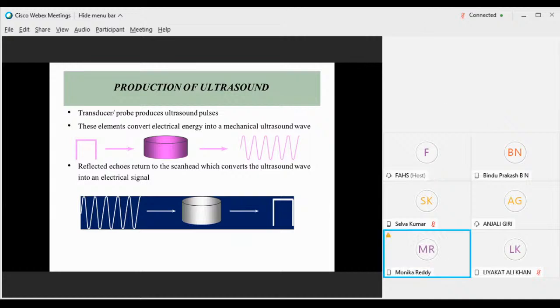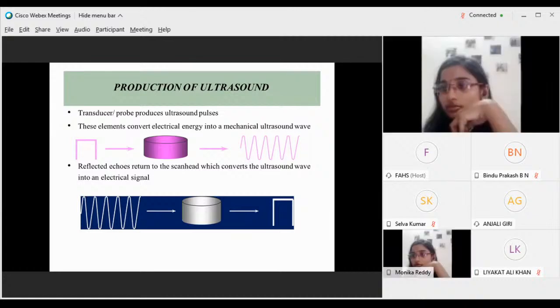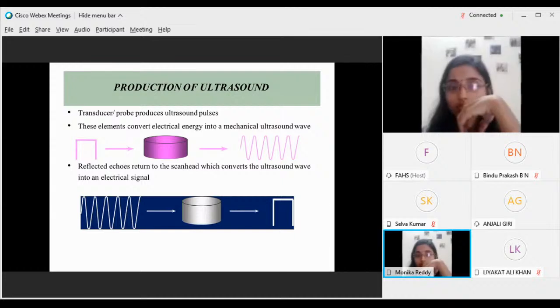Okay. Then comes the production of ultrasound. How will the ultrasound be produced? The transducer probe produces the ultrasound pulses with a vibrating crystal, which is called a piezoelectric crystal. These elements convert electrical energy into the mechanical ultrasound wave. They use the electrical energy and the crystal will vibrate, then it will produce the mechanical ultrasound. And the same happens vice versa: from the body the echo reaches the crystal and is converted to electrical pulses, and shown as an electrical signal on the monitor.